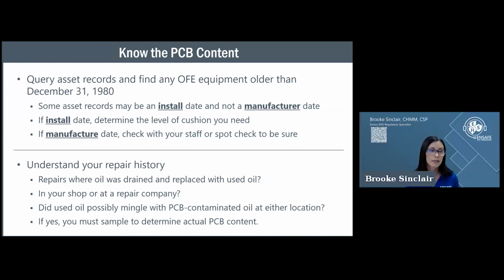So know your PCB content. I mentioned that we queried, and what I recommend is giving yourself a buffer if you don't know the difference between your install and your manufacture date. So think about that as you're talking to your staff. And then I always spot check as well. If I went with manufacturer date, does that actually match nameplate? So do a little spot checking, and then understand that repair history that we talked about earlier. If you did a lot of repairs, if you replaced oil, then you've got to move to sample it as a component as well.